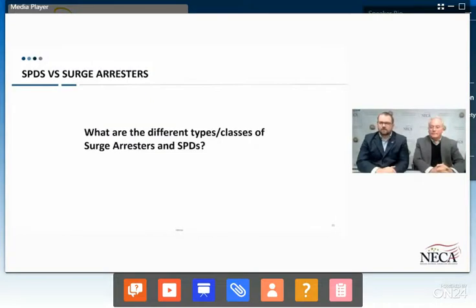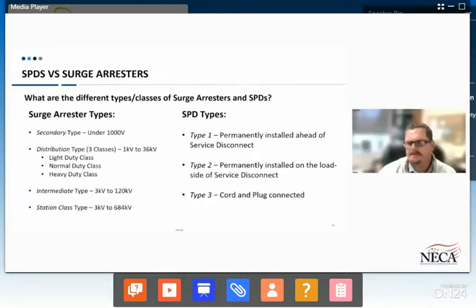Hey, Kyle, can you go through and tell us some of the different types and classes of surge arresters and SPDs to kind of explain that a little bit further? Tell us what's in the marketplace. Sure. Surge arrester types, there's 4 different types. Secondary type, it's going to be under 1,000 volts. Distribution type, 1,000 volts to 36 kV. Intermediate type is going to be 3 kV to 120 kV. And the station class type, 3 kV to 684 kV.